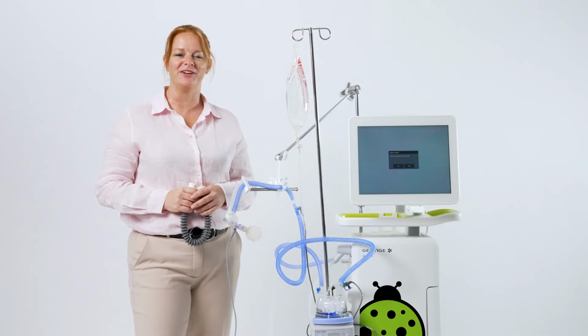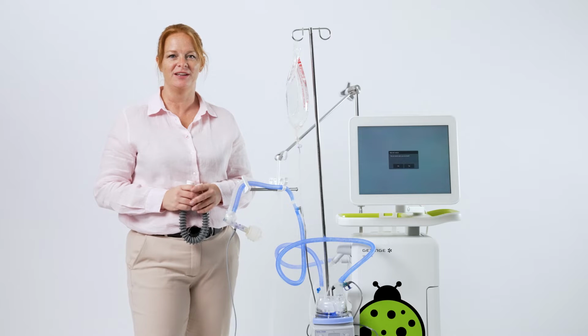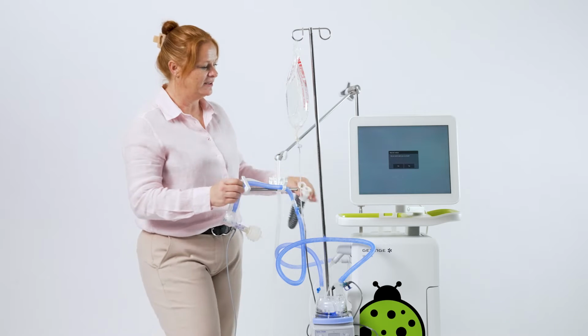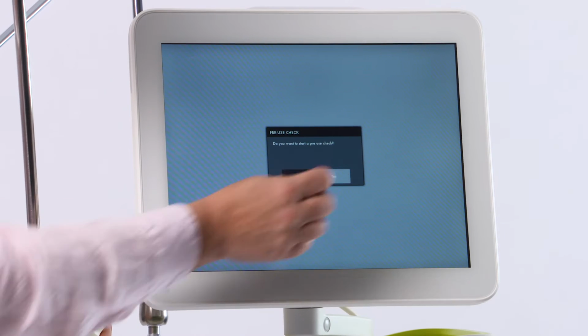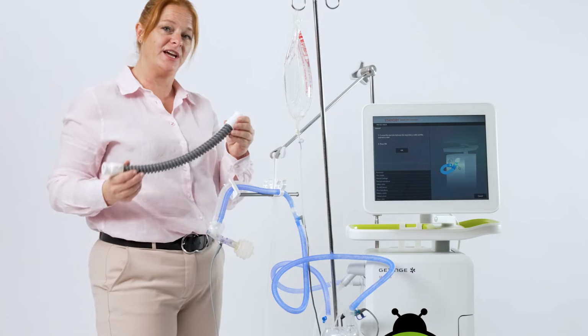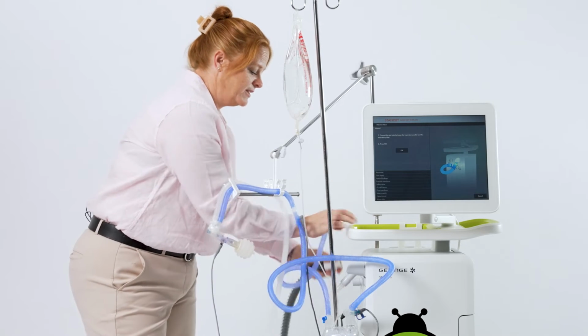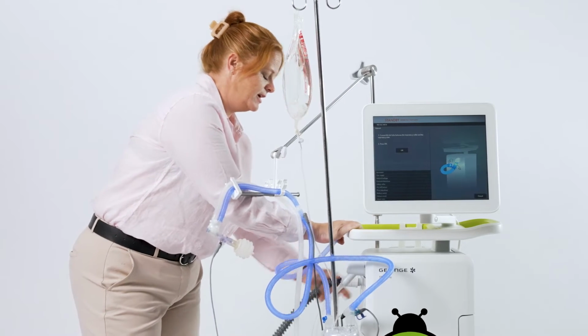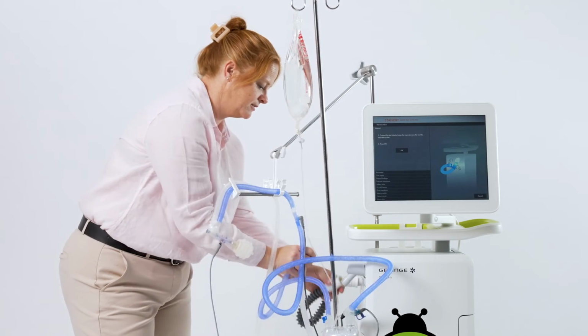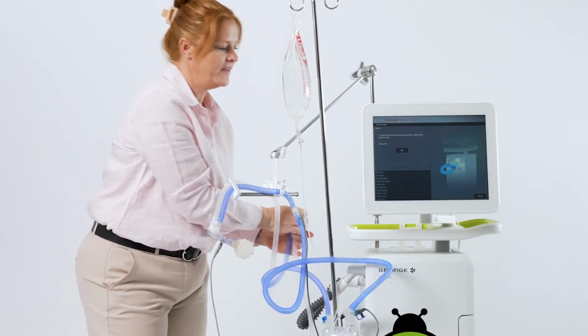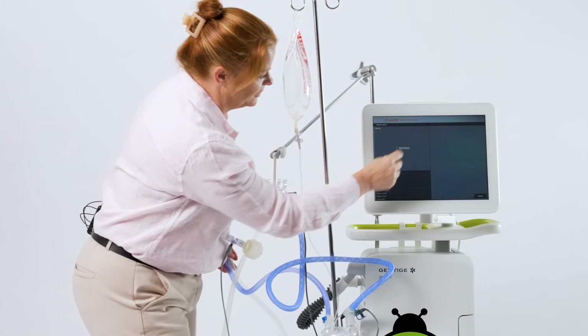Before starting the ventilator, you must first do the pre-use check. It will be prompted on the screen and select yes. First, you must attach the test tube in between the inspiratory outlet and the expiratory inlet. Then press OK, acknowledging.